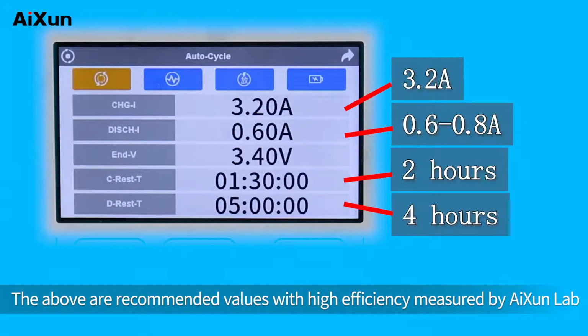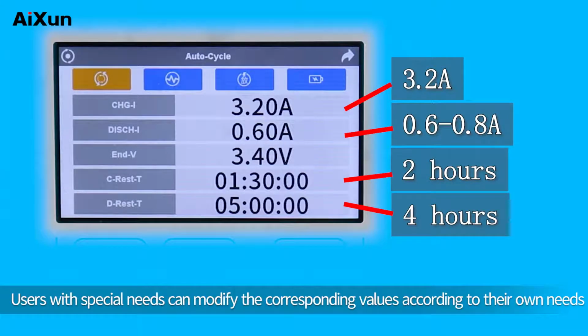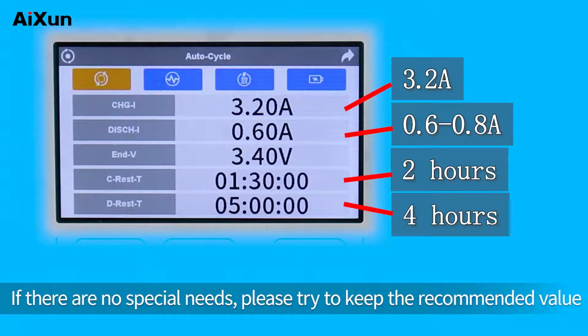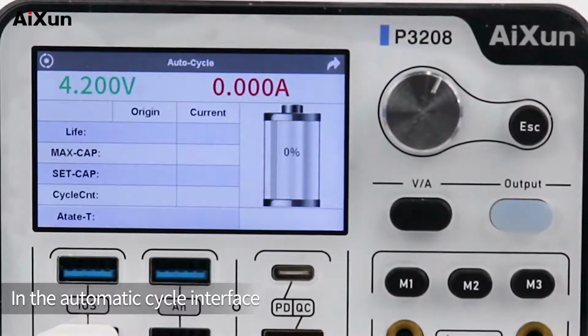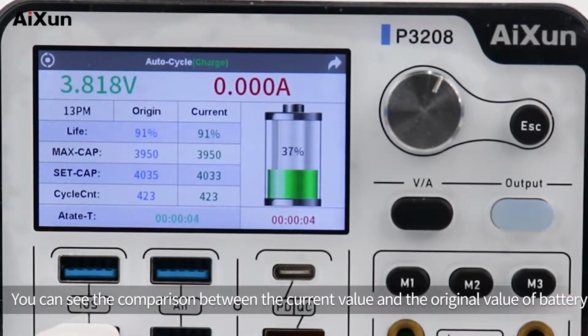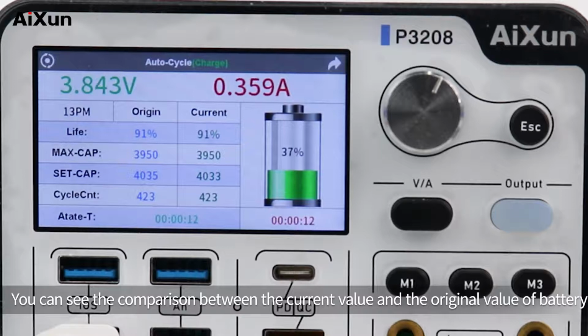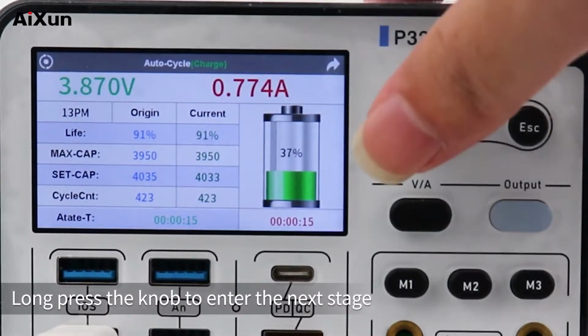The above are recommended values with high efficiency measured by AiXun Lab. Users with special needs can modify the corresponding values according to their own needs. If there are no special needs, please try to keep the recommended value. In the automatic cycle interface, you can see the comparison between the current value and the original value of battery. Long press the knob to enter the next stage.